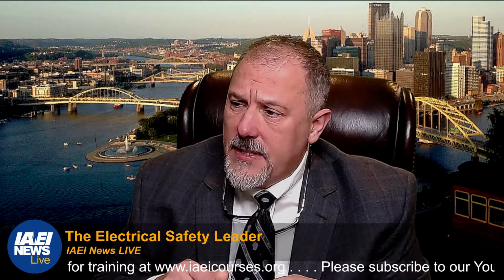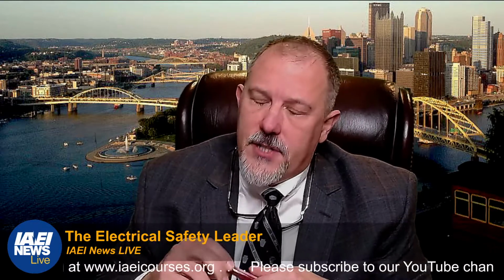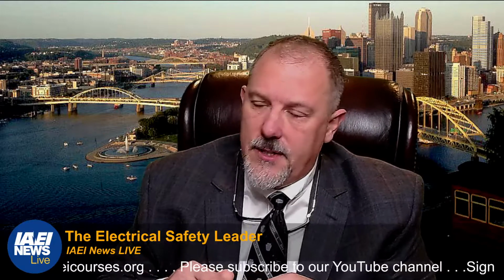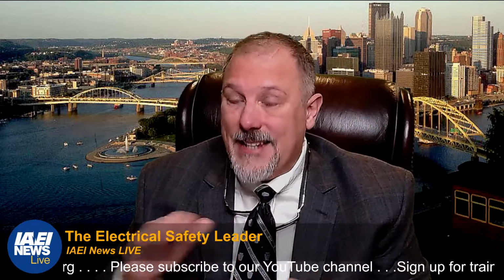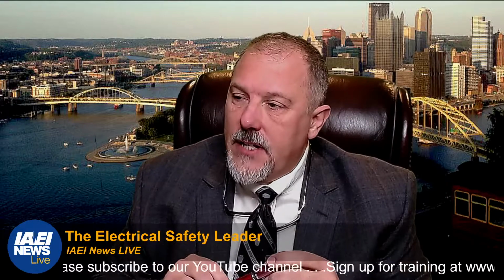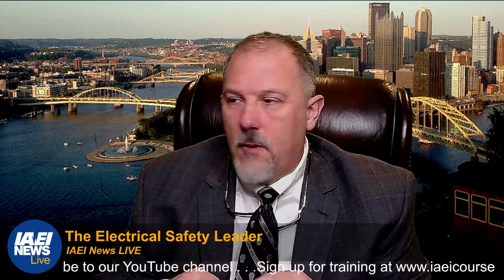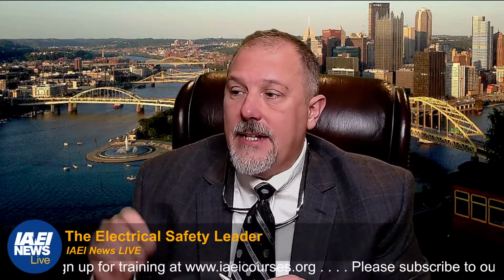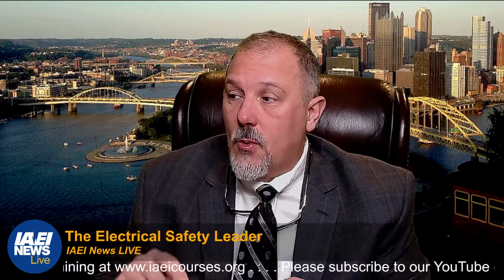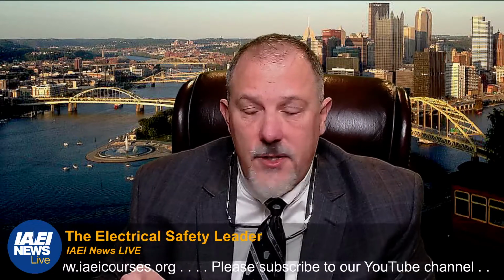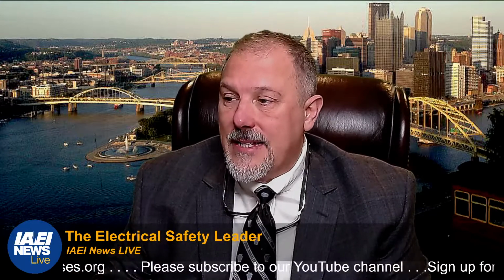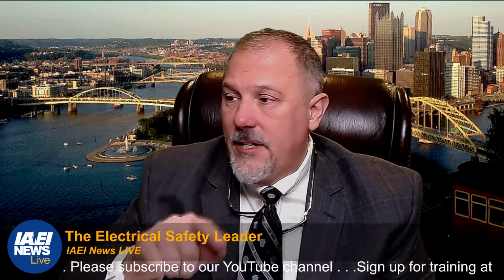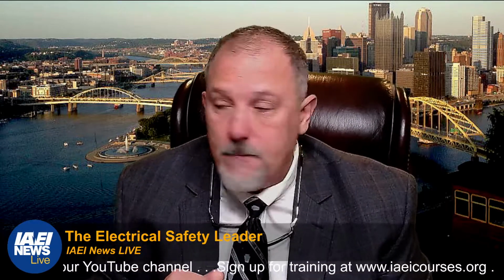So, servicing and maintenance of equipment - a new section in the National Electrical Code says, in the 2023 edition second draft: Servicing and electrical preventive maintenance shall be performed by qualified persons trained in servicing and maintenance of equipment, and shall comply with the following. The servicing and electrical preventative maintenance shall be performed in accordance with the original equipment manufacturer's instructions and information included in the listing information, applicable industry standards, or as approved by the authority having jurisdiction.